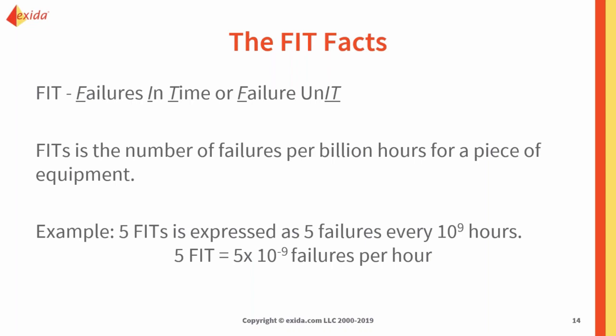When you hear people talking about failure rates in general, or saying they got this failure rate from a certificate or from an FMEDA, they're generally talking in terms of FITs. And FITs can be broken up into safe or dangerous, detected or undetected failures. They're really important pieces of information for end users. The failure rates, usually in FITs, are what go into a lot of the SIL verification calculations, such as PFDavg or PFH. So it's imperative not only that these failure rates are correct, but also that they are for the right application, the right operation, the right demand, and that they are realistic.